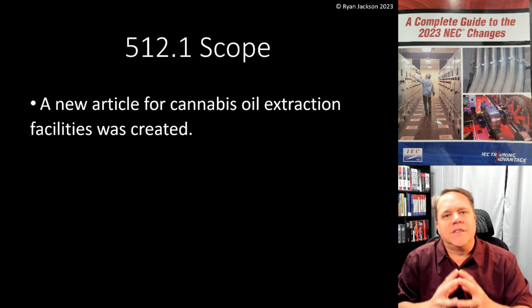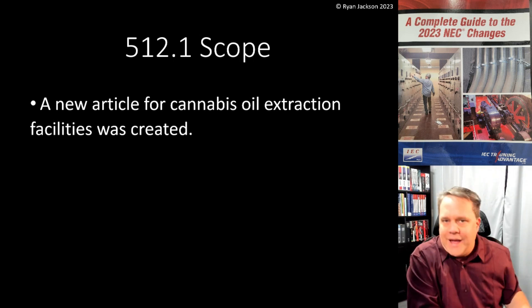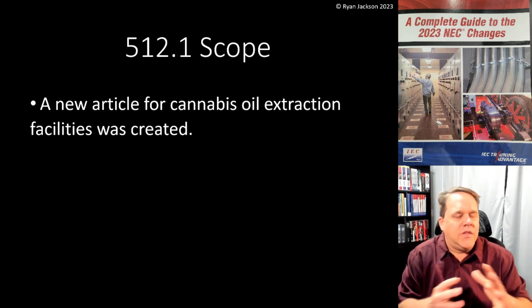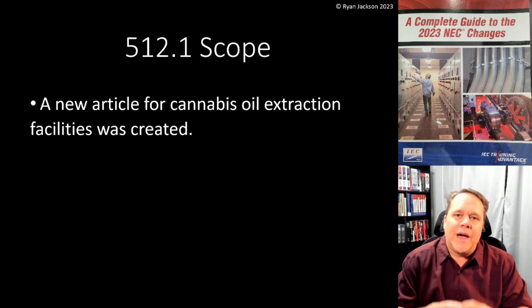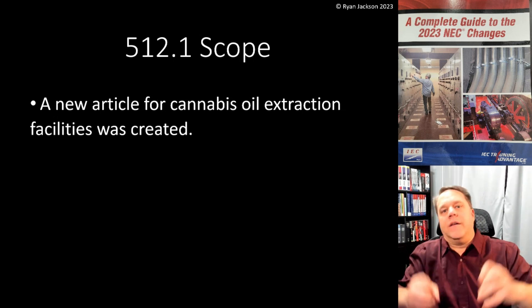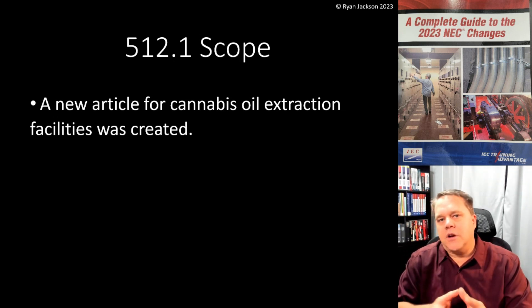The NEC does not typically classify locations for you. If you're doing an oil refinery or a coal-fired power plant, you can't just open up the NEC and say within 12 inches of this equipment it's this classification. That's not the way the NEC works. The NEC says you're going to have to have a design team and figure out how to classify the area — do you have normally ignitable mixtures under normal conditions or only under abnormal conditions? Do you have suspensions of combustible dust or layers of combustible dust? The NEC doesn't do it for you, except in a couple of instances.